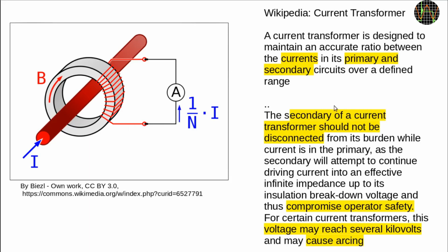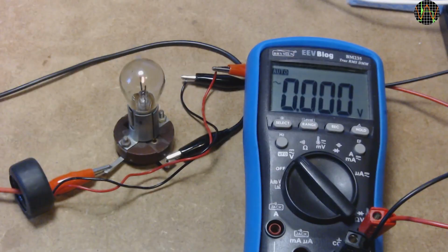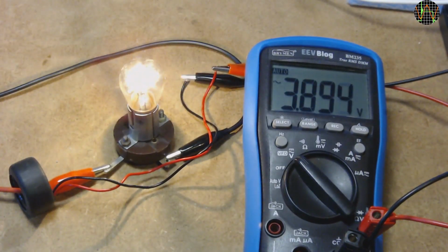Obviously, we are supposed to measure the current in the coil and not the voltage that is induced. In fact, there's a section here that warns one should not disconnect the burden, that is the ammeter, or you may get kilovolts and arcing. Exciting stuff. The current in the lead going through the coil to the bulb is about 1.4 amps.